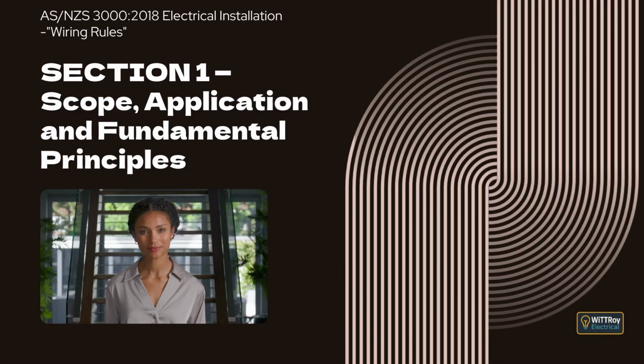Clause 1.4.62 is exposed conductive part. This is a conductive part of electrical equipment that Item A. Can be touched with the standard test finger as specified in AS/NZS 3100, and Item B. Is not a live part, but may become live if basic insulation fails. There are exceptions where the term does not apply. These include conductive parts inside an enclosure where a key or tool is needed to open it. Conductive parts inside equipment that cannot be touched in normal use or during normal movement of the equipment. Conductive parts that are separated from live parts by double insulation or by conductive parts that are already earthed.